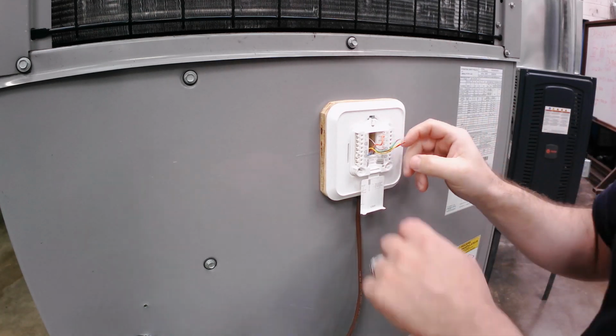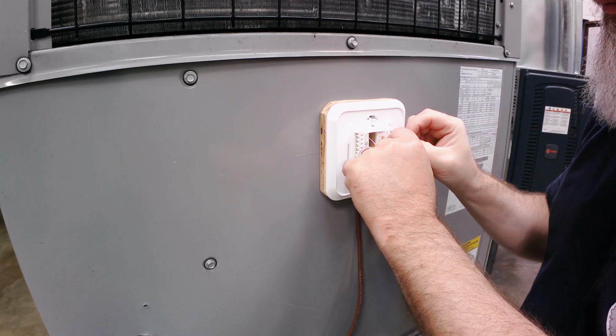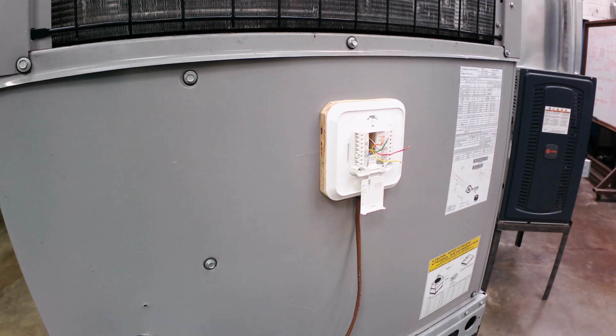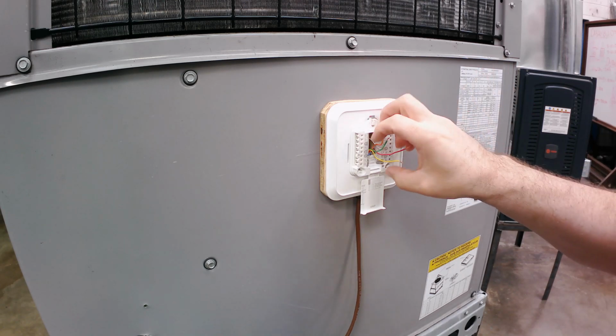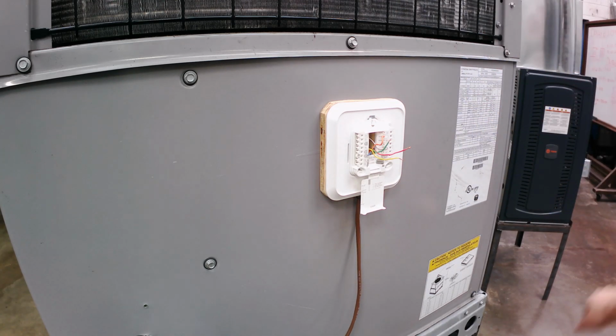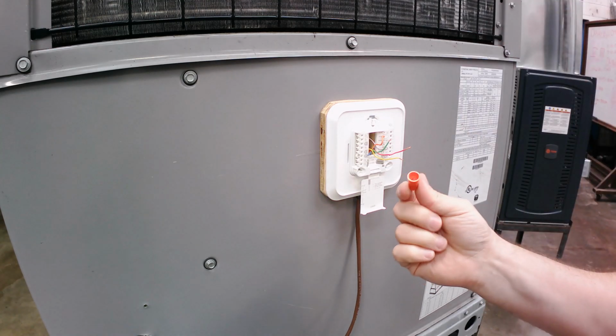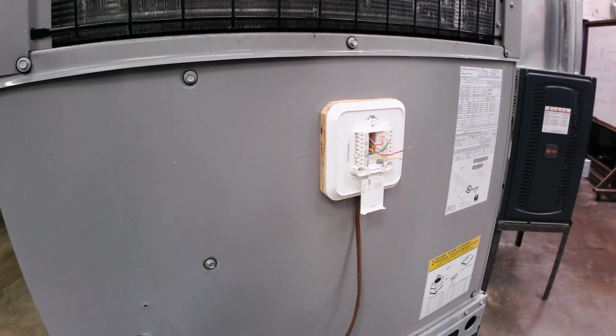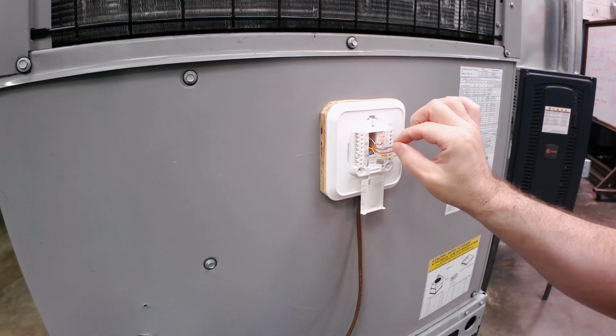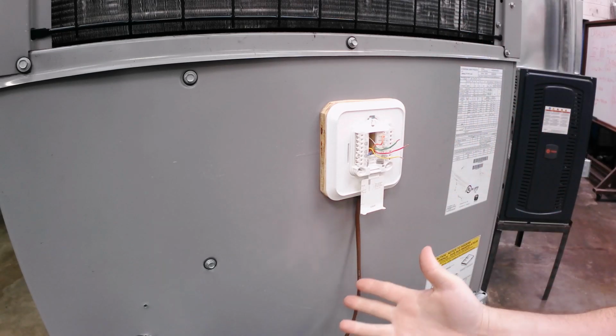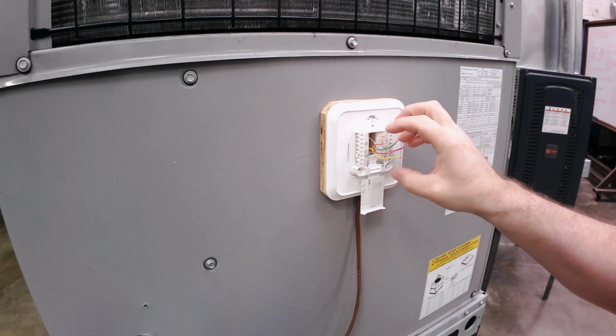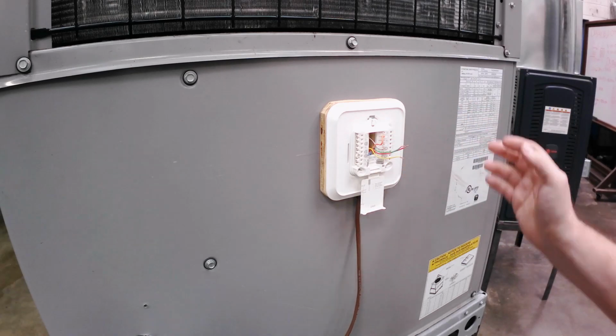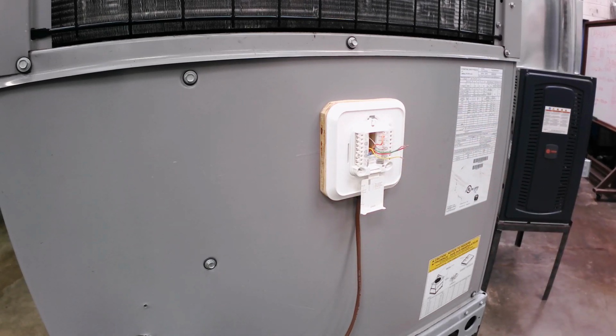Hopefully you get that. If you take all those wires and jump them all together, everything in the system should run. We can make the heat and cool run at the same time if we wanted, because we are truly controlling that switch. The thermostat is going to be broken down into heat and cool, not everything at once. But if you ever think your thermostat is a problem, troubleshoot it properly. You can use a little cheap trick like a wire nut to make everything work, so you can finish diagnosing the system in its entirety.